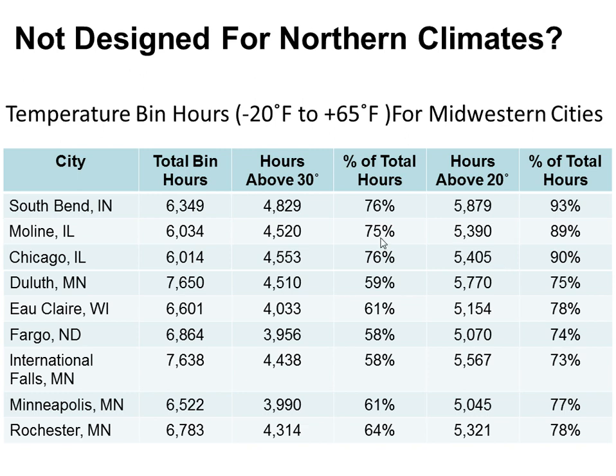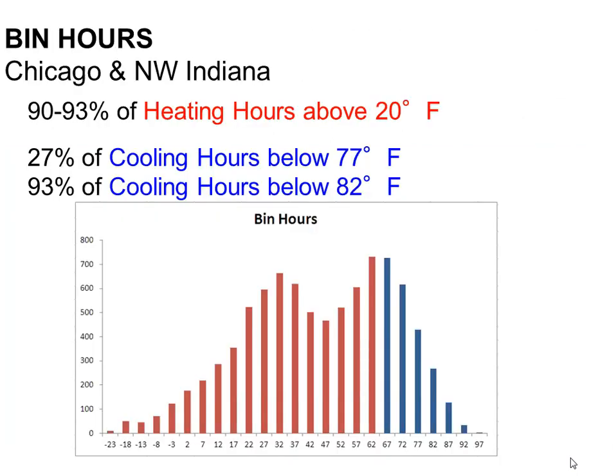And then to give you some more extreme examples, if you just look at this chart, some of the colder places that we ever think about, in the Midwest here, like up in Minnesota or International Falls, right? That's the place on the weather map that they always show you as the coldest place, right? It's always got the -20 degrees. Even then, look how many hours they have, 4,500 run hours above 30 degrees, 5,500 hours above 20 degrees. Yeah, they get a bunch of -20 degree days, but it's not very many hours of operation. So we have plenty of time that we can run heat pumps in our climate for cold weather.